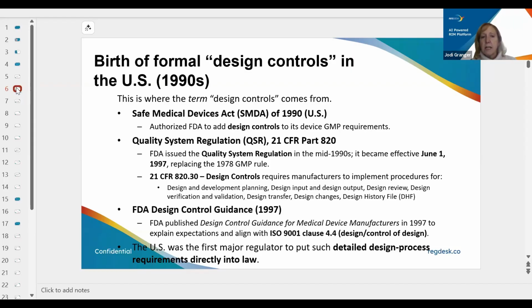The QSR regulation came after that, and the original was in the mid 1990s, and it became effective in 1997. 21 CFR 820.30 was updated for design controls explicitly, and this started the requirement for manufacturers to implement procedures specific to the whole design control process. So that included design and development planning, how you generate your design inputs and outputs, having processes in place to have formal design reviews, the requirements for design verification and validation, how you do design transfer.